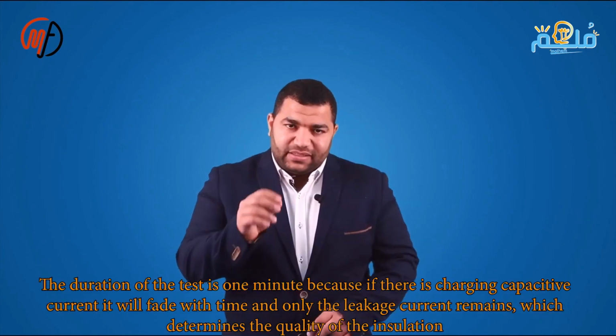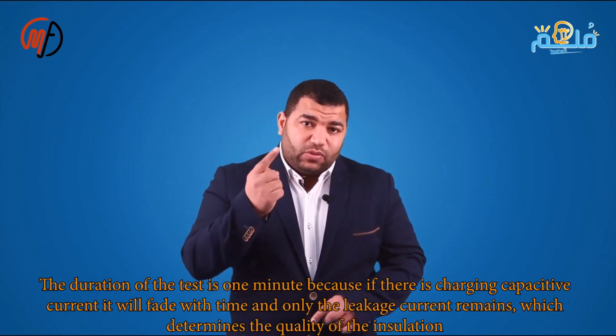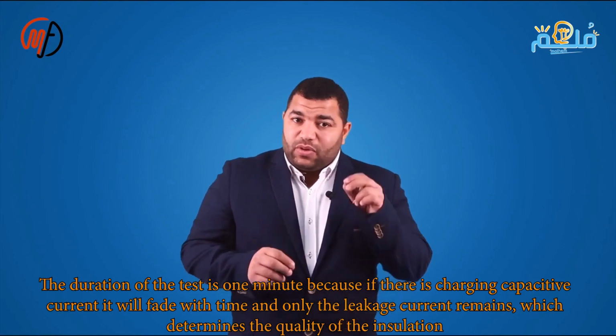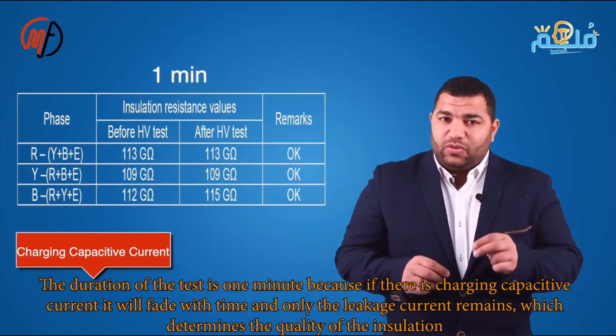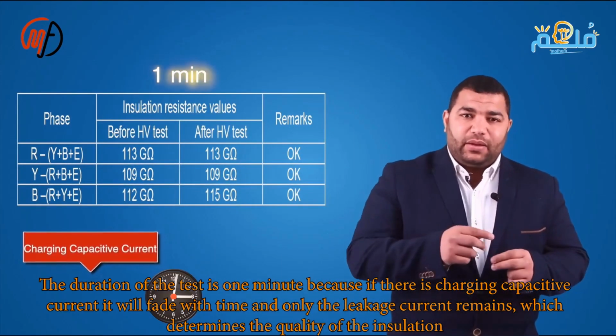The CT IR test involves applying DC voltage, 5 kilovolts from primary to ground, 1 kilovolt from primary to secondary, and 1 kilovolt from secondary to ground or secondary to secondary, all for 1 minute.